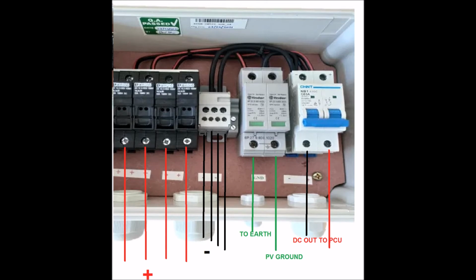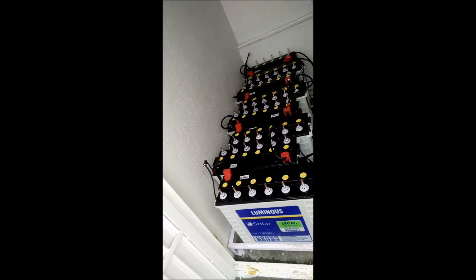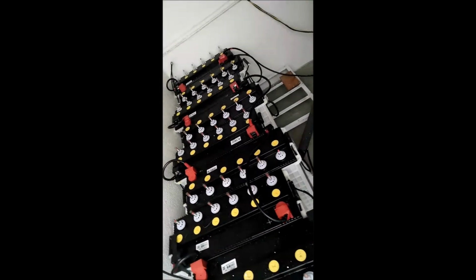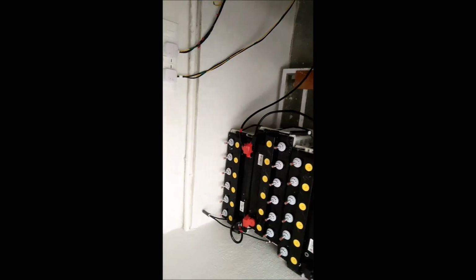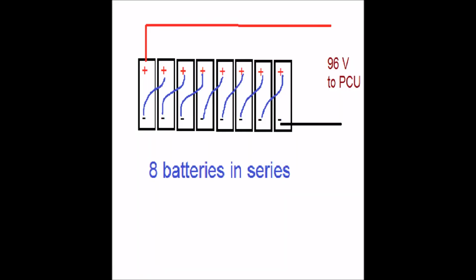Finally, the output wires from DCDB going to be PV input to PCU are taken from DC MCB. These are 10 square mm wires. 8 batteries are connected in series to get a 96 volts output. 16 square mm goes into the PCU.